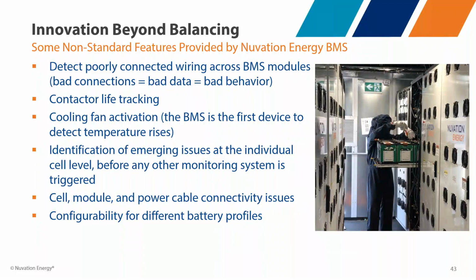This again is a feature that we've implemented in software, and we've had really good success in the field with customers using this algorithm. For example, when we first bring a system online, we log into the system and do open wire detection across the system, and it can actually detect slightly higher resistances inside of a system. We've had it where we bring up a totally new container, and we tell the customer, hey, in stack 3, cell 17, that bolt must not be correctly torqued because we're seeing a notably higher open wire result. And the customer goes over and puts a wrench on it, and sure enough, that wanted a quarter turn on that bolt. So it's actually a really useful algorithm.